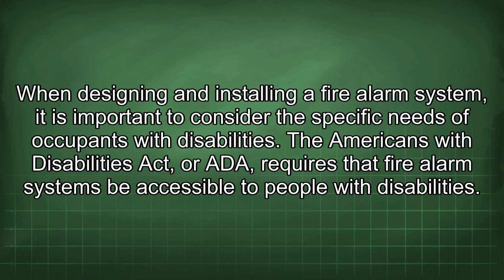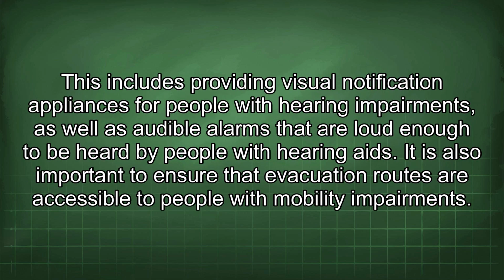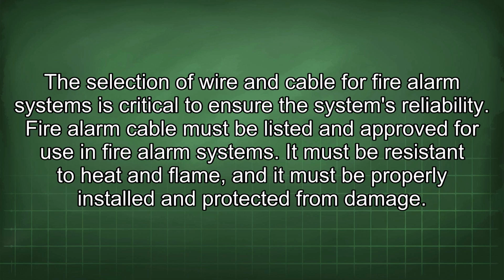When designing and installing a fire alarm system, it is important to consider the specific needs of occupants with disabilities. The Americans with Disabilities Act, or ADA, requires that fire alarm systems be accessible to people with disabilities. This includes providing visual notification appliances for people with hearing impairments, as well as audible alarms that are loud enough to be heard by people with hearing aids. It is also important to ensure that evacuation routes are accessible to people with mobility impairments. The selection of wire and cable for fire alarm systems is critical to ensure the system's reliability. Fire alarm cable must be listed and approved for use in fire alarm systems.